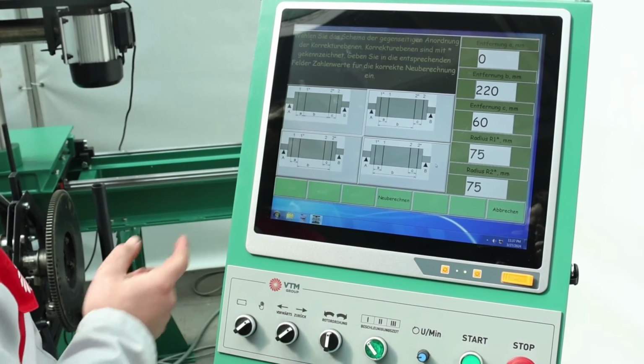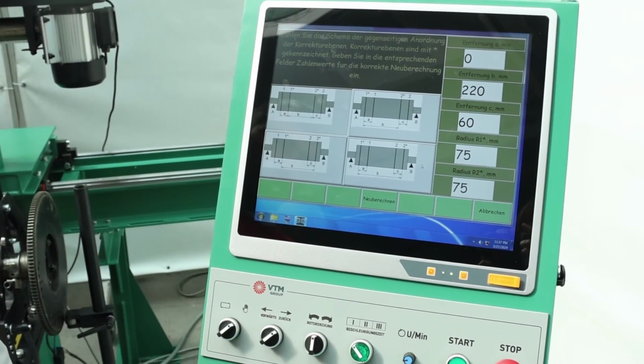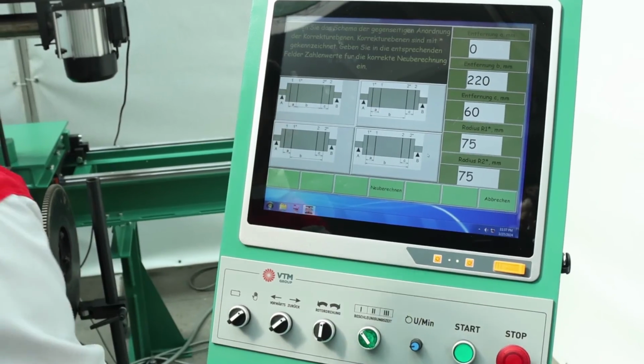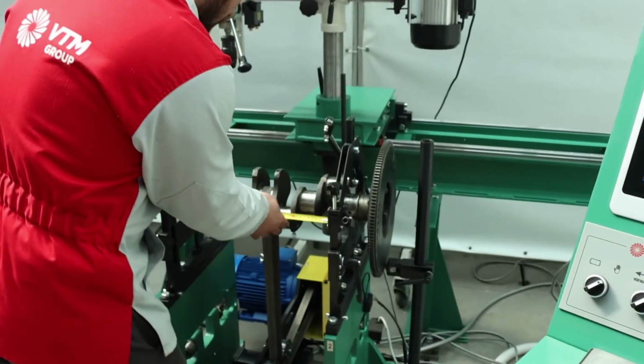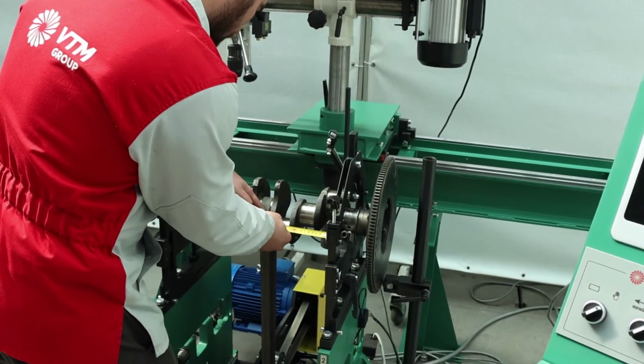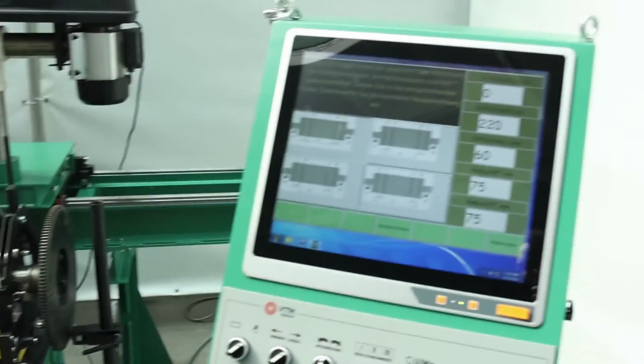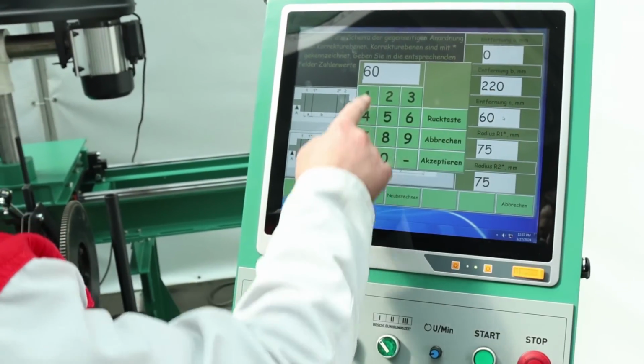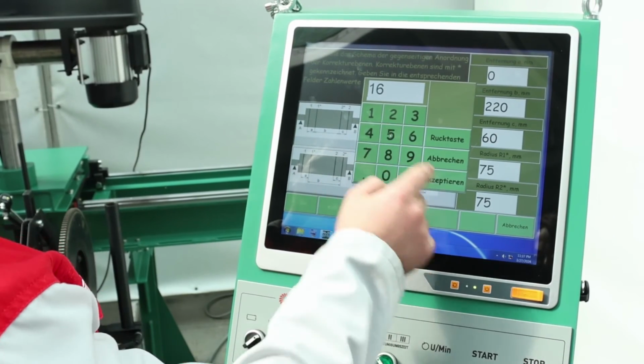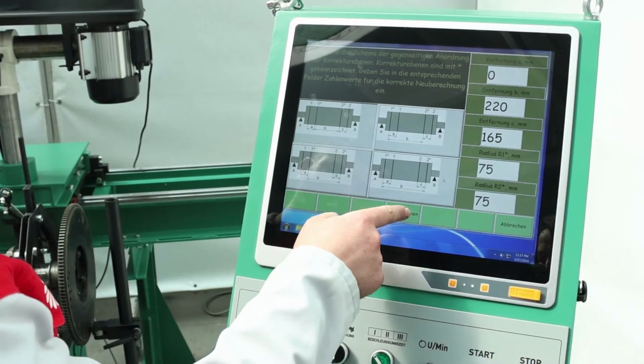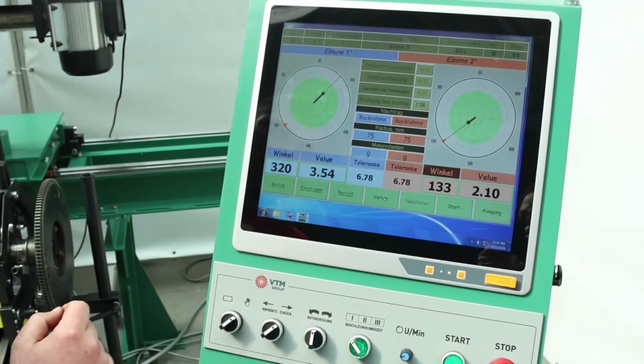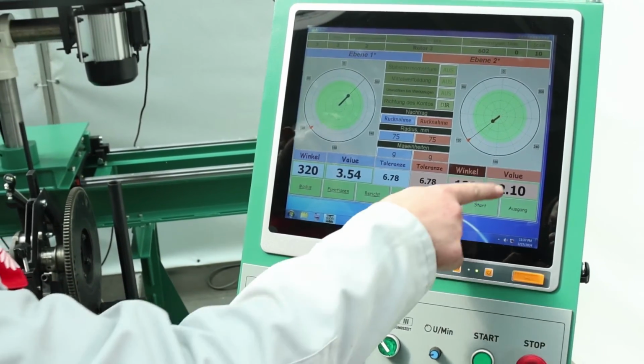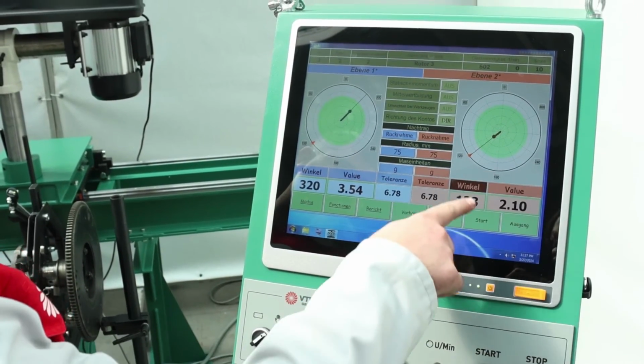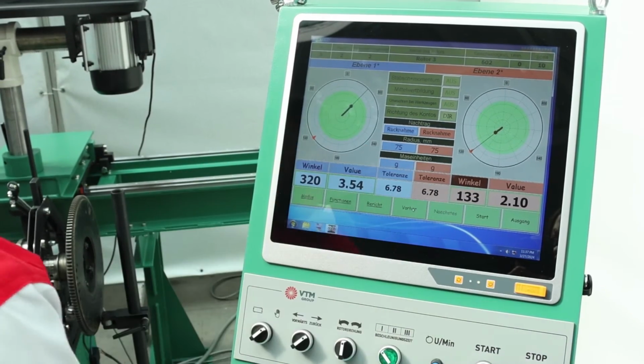And the distance C is from the old second correction plane to the new second correction plane. We have it set at 165 millimeters. We press the confirm button and press the calculate button. Then we can see how much unbalance in grams we need to remove from the new second correction plane.